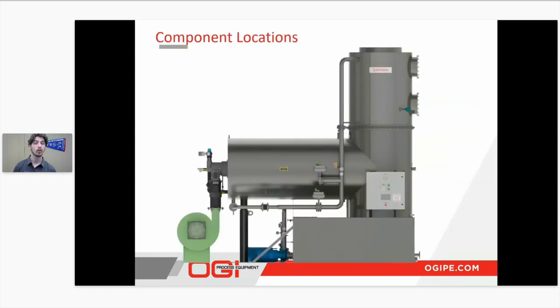Going over some component locations briefly on the QuikWater, we'll start from left to right. We start with our chamber high temperature switch. This is going to be monitoring the chamber temperature as it's going across. It makes sure you're not overheating in any regard for the burner overfire. Both our recirculation valve and our inlet valve are going to be modulating on and off depending on the heater, whether you're feeding fresh city water in through your inlet valve or you're recirculating the water within the tank to get back up to temperature after a point of non-usage.